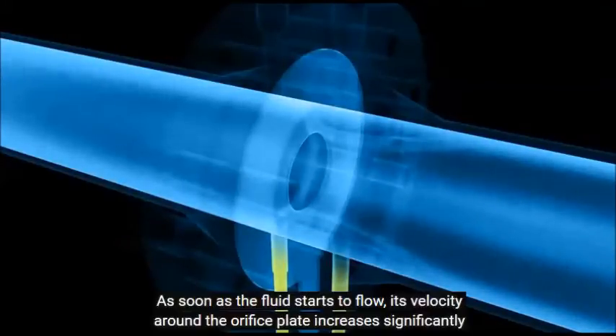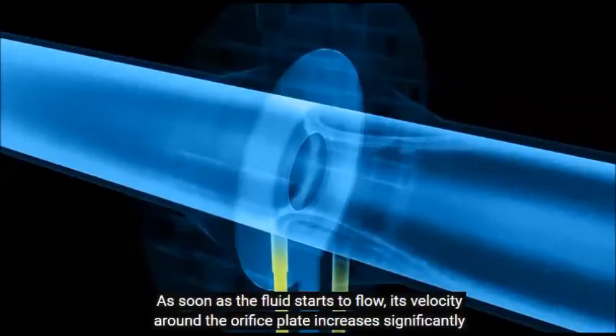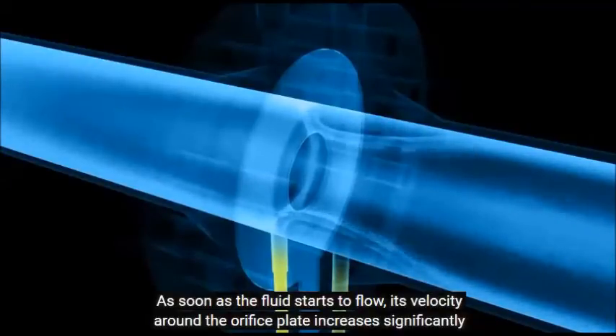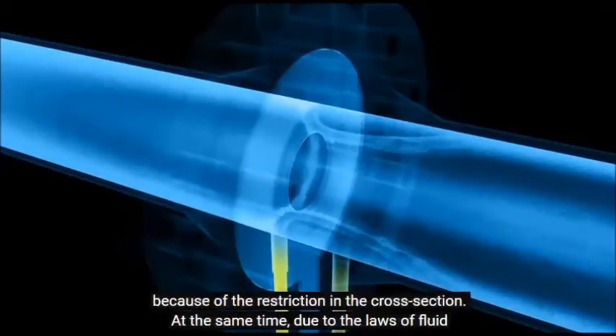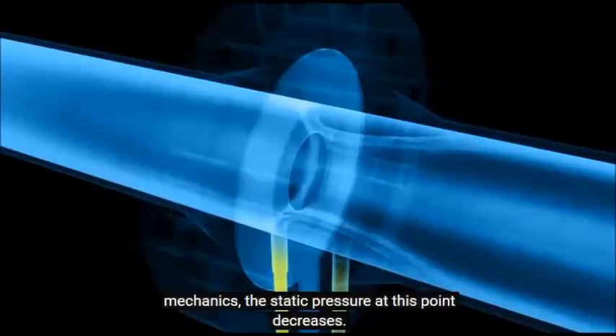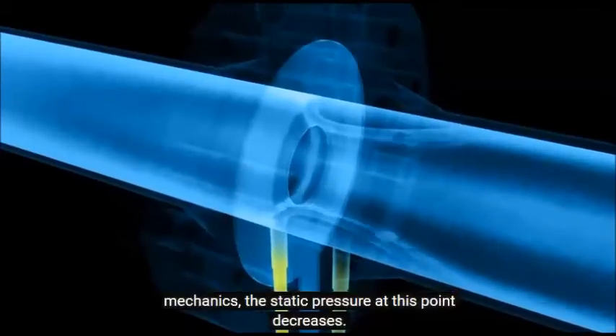As soon as the fluid starts to flow, its velocity around the orifice plate increases significantly because of the restriction in the cross section. At the same time, due to the laws of fluid mechanics, the static pressure at this point decreases.